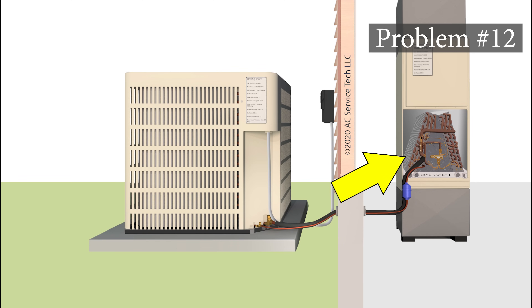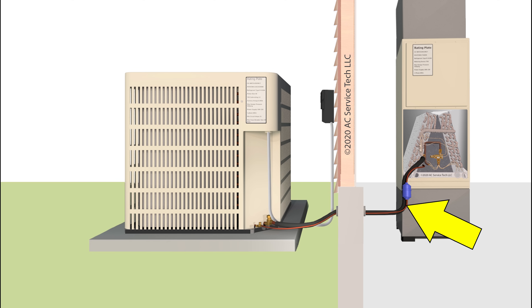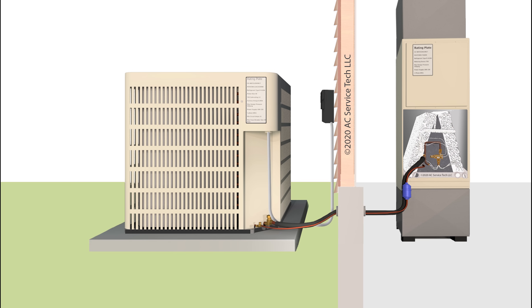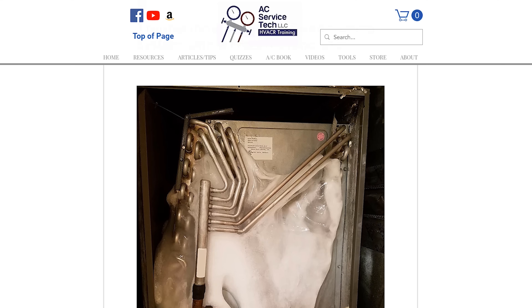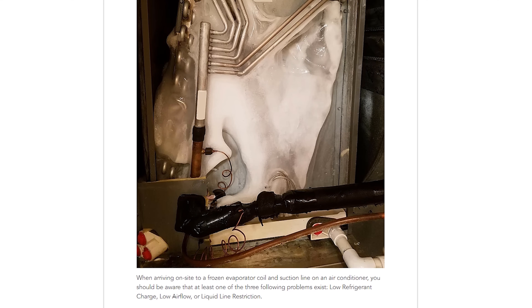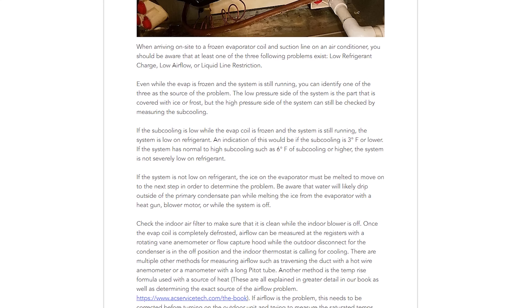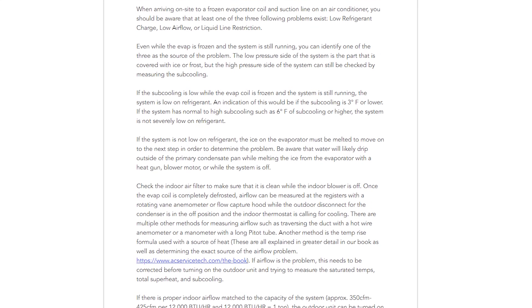You could also have a frozen evaporator coil, which is usually due to one of three things: a low refrigerant charge, a liquid line restriction, or pre-existing low airflow. Obviously, with a frozen coil you now have no airflow at all. Check out the article on our website that differentiates between low refrigerant charge, low airflow, and liquid line restriction.